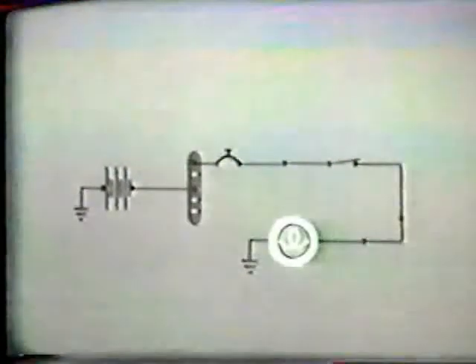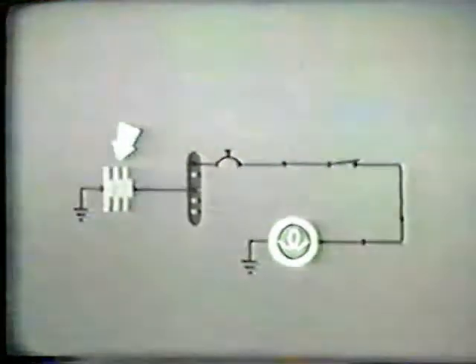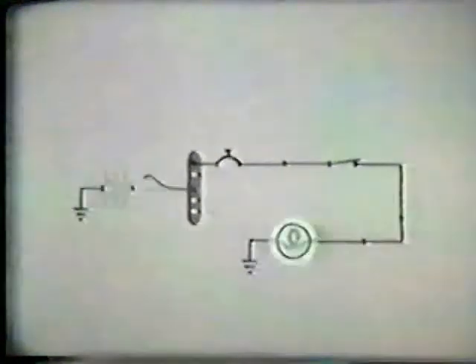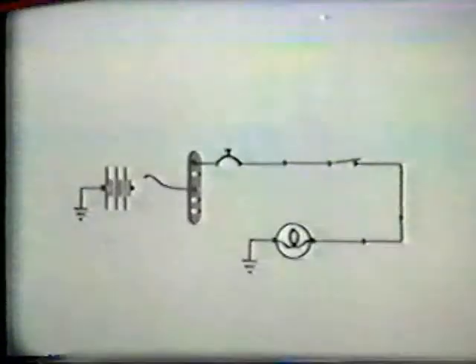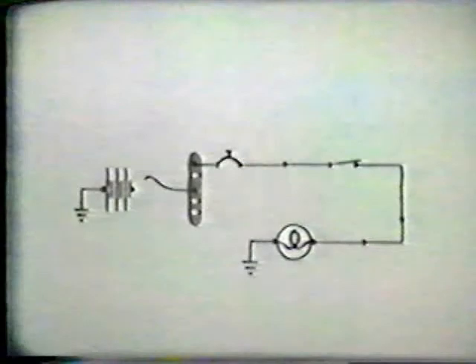The most important thing to remember is this. The circuit must be disconnected from its source of power before connecting the ohm meter. You can do this by turning the switch off, or by pulling a circuit breaker. But the best way is to disconnect the battery. The important thing is to be sure the circuit is dead before you connect your ohm meter. If you connect an ohm meter to a live electrical circuit, you will burn out the meter.